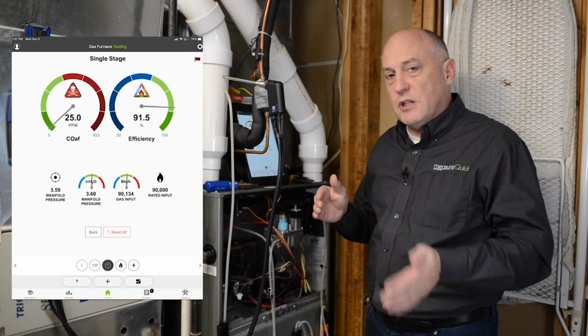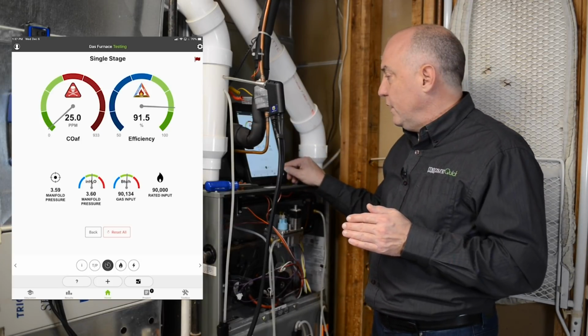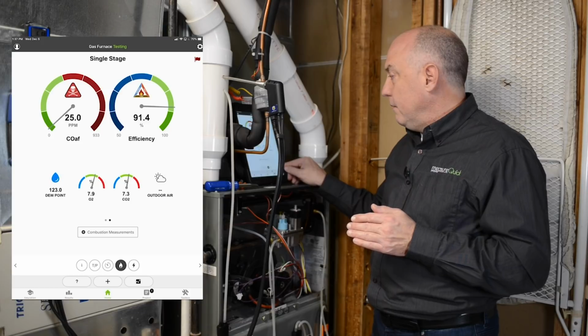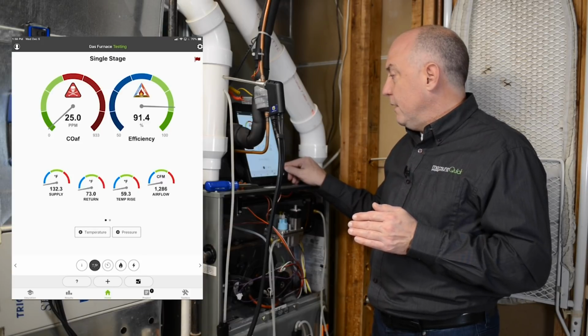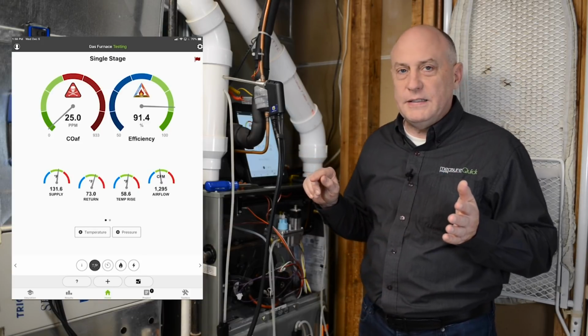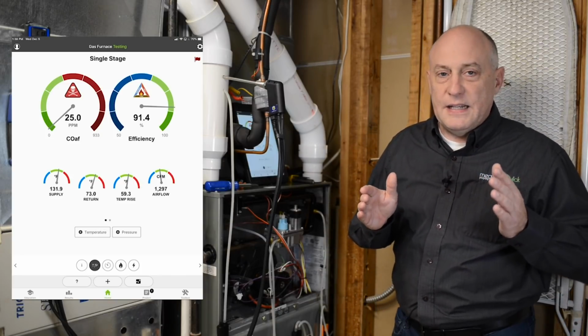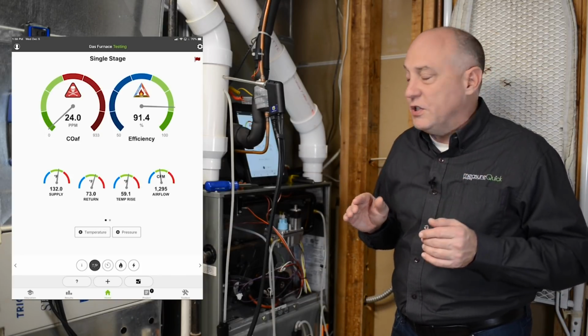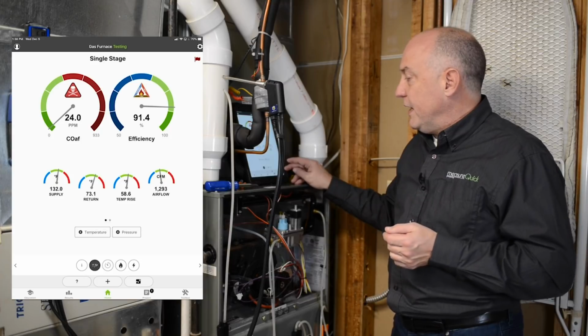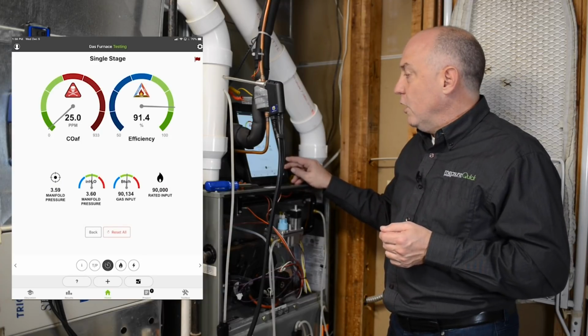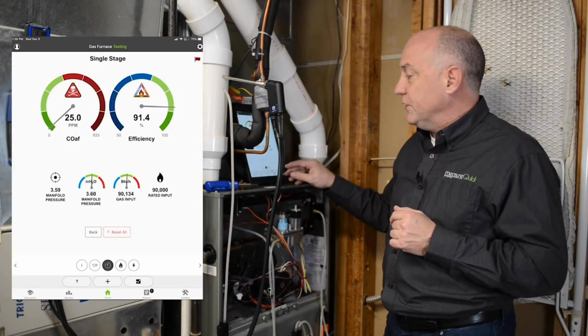My return air temperature is up a little bit high right now. If we scroll through to that, we'll see that my return air temperature is about 73 degrees, and that will affect the condensing of the appliance, and that's why we're seeing the efficiency drop down a little bit. But everything else looks pretty good. So as we go through here, again, manifold pressure, all those things done.